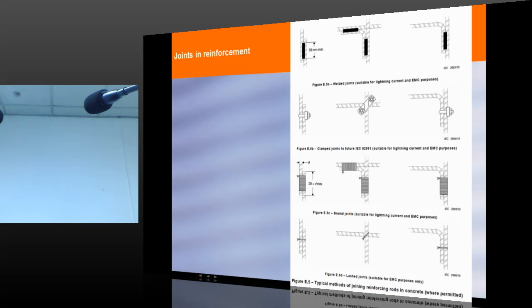This clause can be avoided if you do an exothermic welding, and this exothermic welding should then satisfy some points of the standard: mechanical strength, the current handling strength. Then the third one is freeze-thaw and other tests, because maybe at 0 degree it should not break, at 50 degree it should not lose or something like that. So all those conditions it has to meet. Welding is the best. Second best is a clamp. But not only the clamp, including rebars need to be tested.